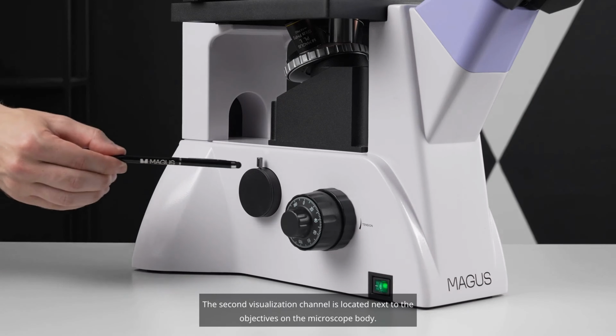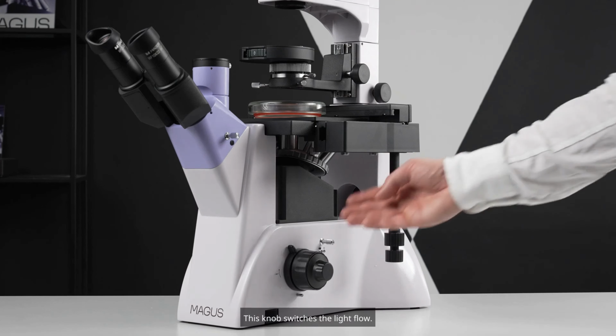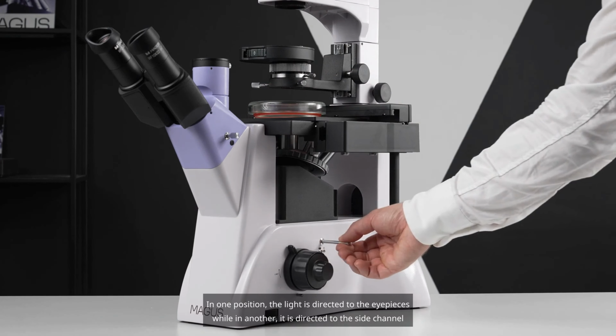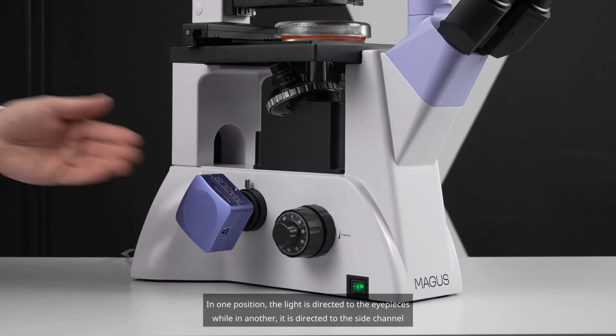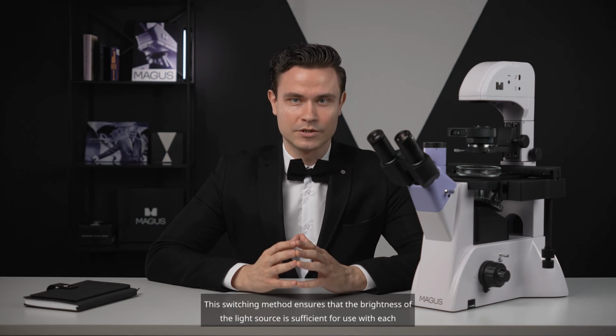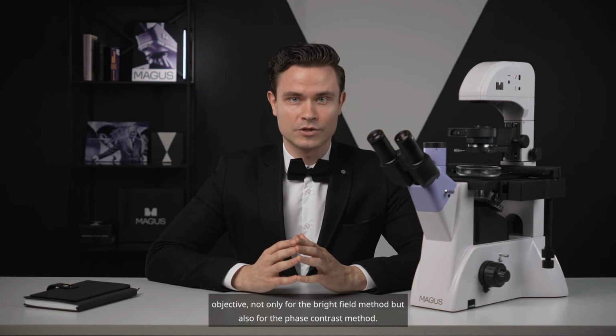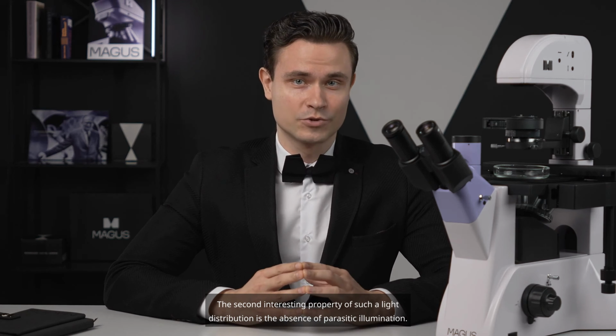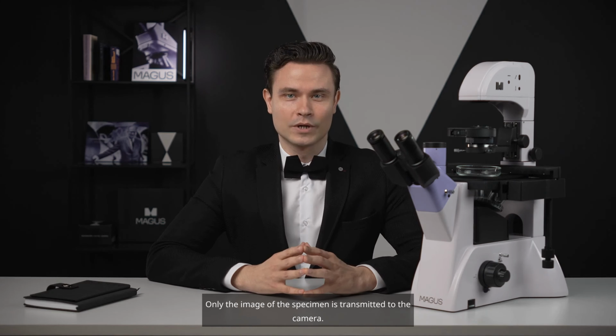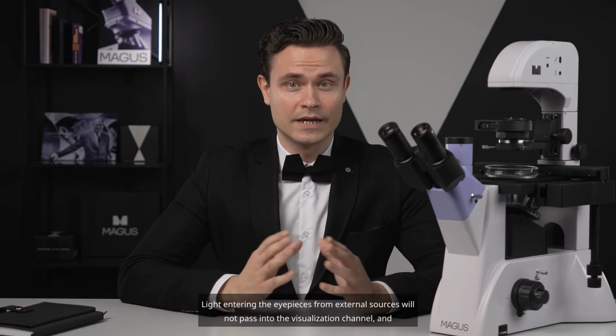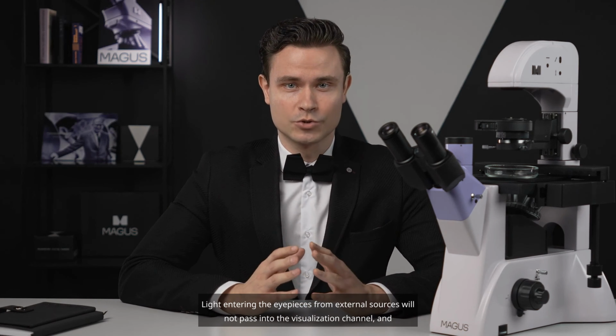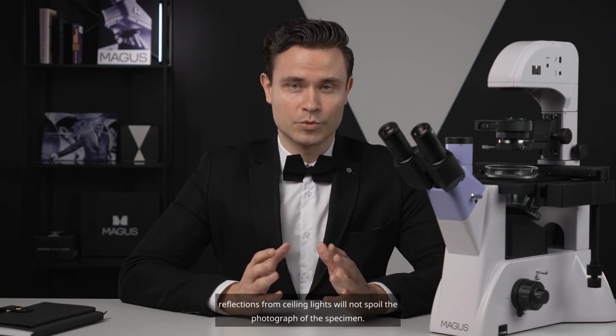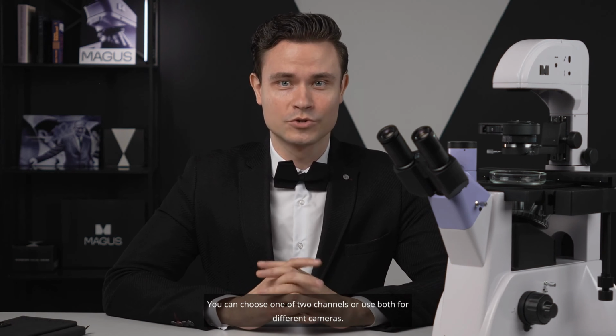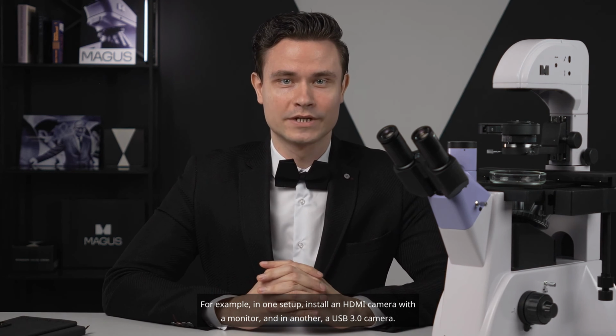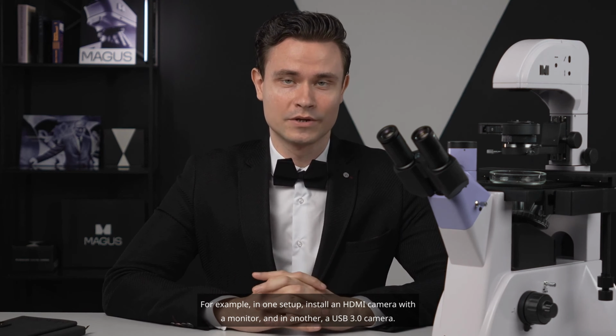The second visualization channel is located next to the objectives on the microscope body. This knob switches the light flow. In one position, the light is directed to the eyepieces, while in another, it is directed to the side channel. This switching method ensures that the brightness of the light source is sufficient for use with each objective, not only for the bright field method, but also for the phase contrast method. The second interesting property of such a light distribution is the absence of parasitic illumination. Only the image of the specimen is transmitted to the camera. Light entering the eyepieces from external sources will not pass into the visualization channel, and reflections from ceiling lights will not spoil the photograph of the specimen. You can choose one of two channels or use both for different cameras. For example, in one setup, install an HDMI camera with a monitor, and in another, a USB 3.0 camera.